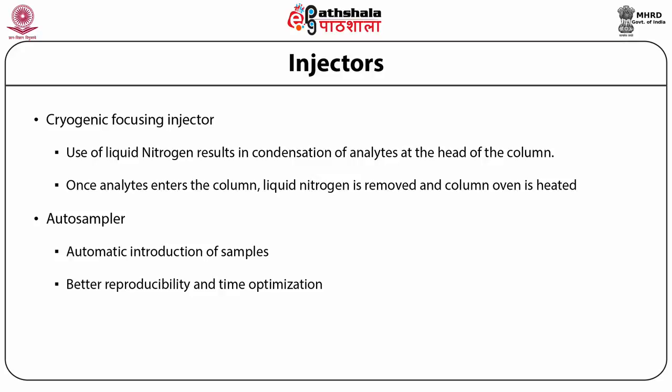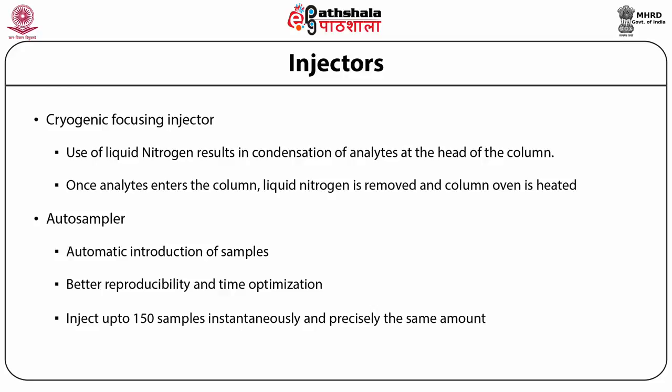For any experiment, its validity stands upon the reproducibility of results. While handling low volume samples, chances of error are high with manual loading. To overcome this, auto-samplers are used in gas chromatographic machines. Auto-samplers can inject up to 150 samples instantaneously with precisely the same amount of sample every time, consistently reproducing small volume injections and saving considerable labor cost and time.